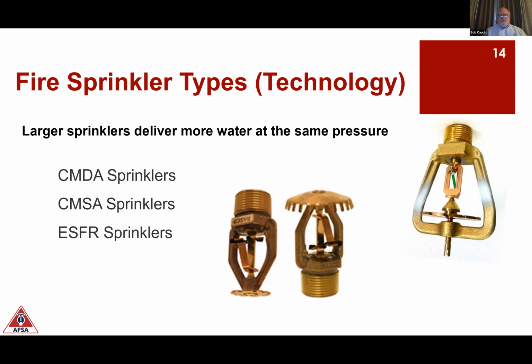CMDA, which is called control mode density area sprinklers. They're standard sprinklers. If you're in the office building right now, look above your head. You're looking at a chrome semi-recessed or chrome pendant sprinkler. That's a control mode density area sprinkler. The sprinkler is designed to control the fire and limit its regrowth. It's not designed to extinguish the fire, although that does happen more often than not.